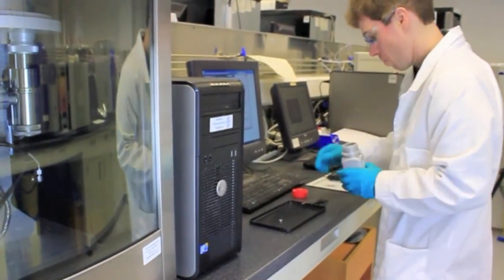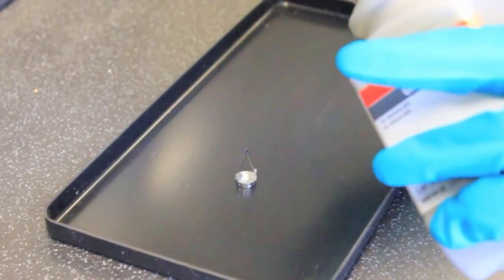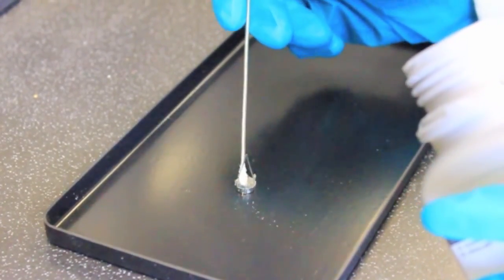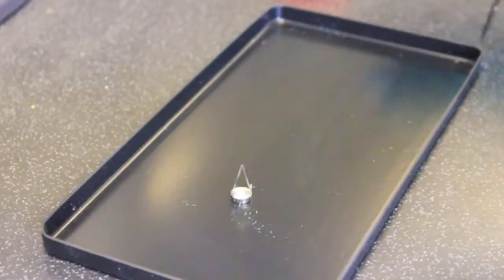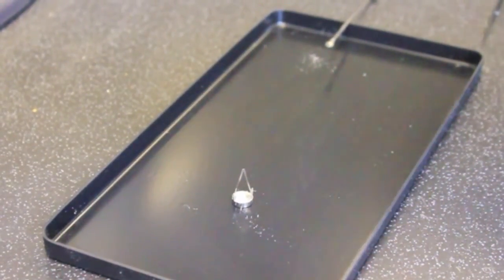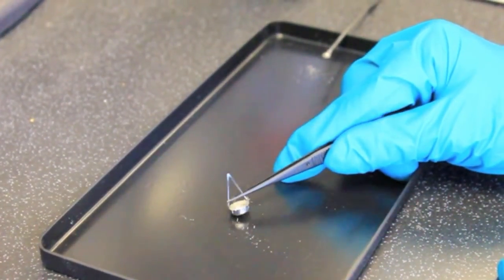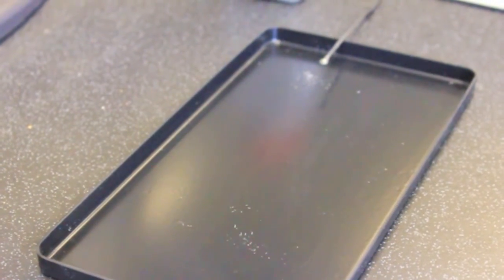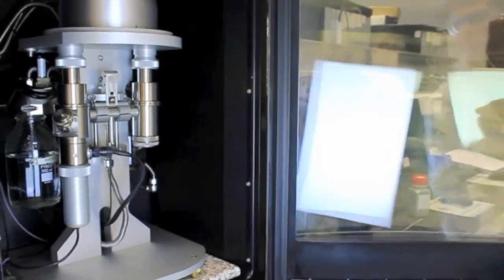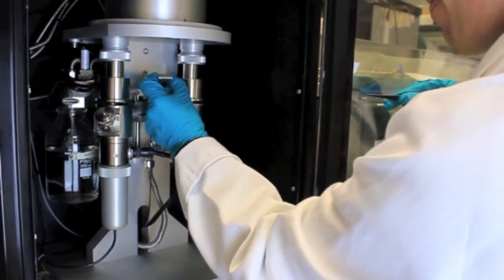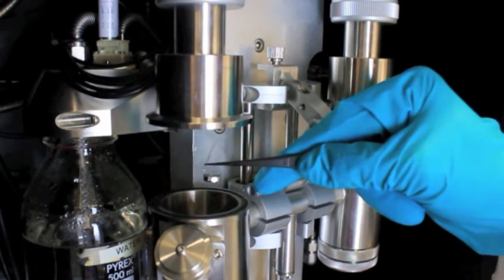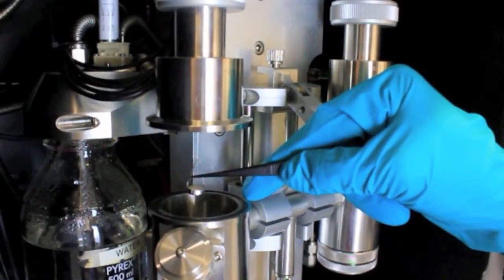Let me explain how the DVS method works practically. We start by taking a small amount of sample — typically about 10 milligrams, which is the size of a rather large match head. That's all the material we need to do a full characterization. We take that material, put it in a small glass pan, and attach it to a very sensitive microbalance. In the DVS instruments, we use microbalances with a resolution of 0.1 microgram, and they can measure mass changes up to one gram. We're able to measure very small changes in sample mass, and that small sample will be exposed at a constant temperature to a user-selected humidity.